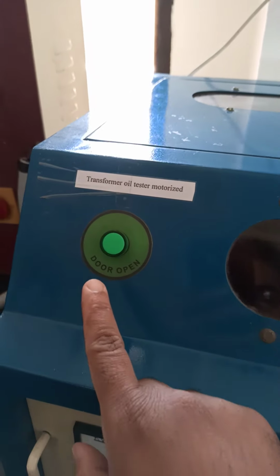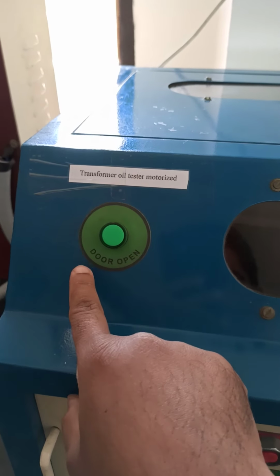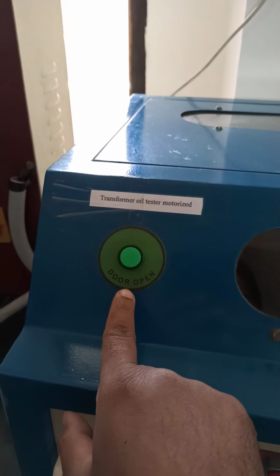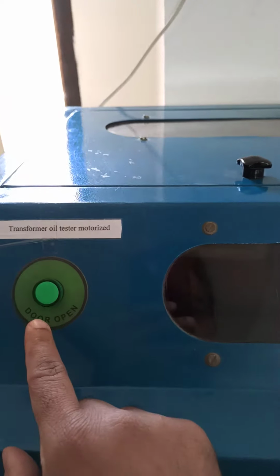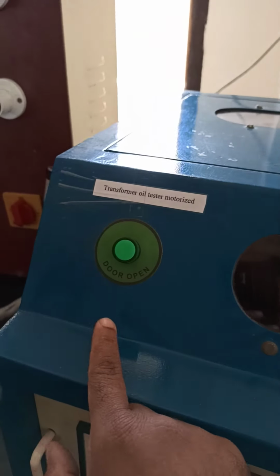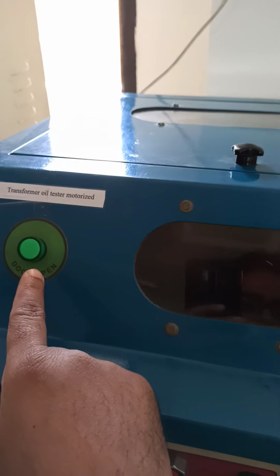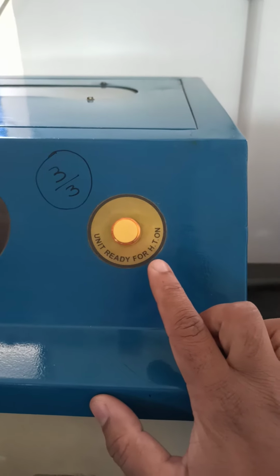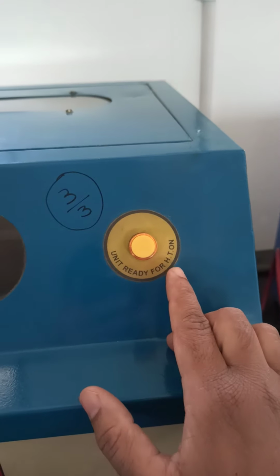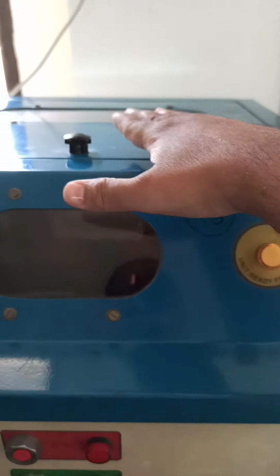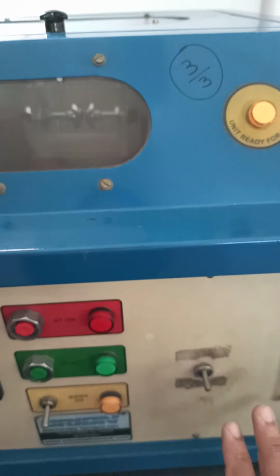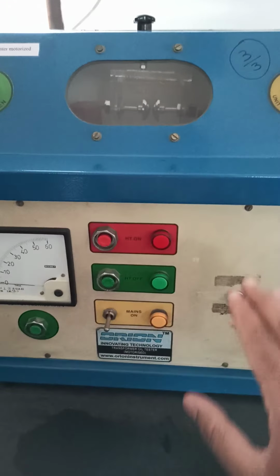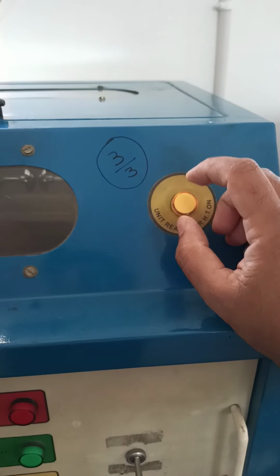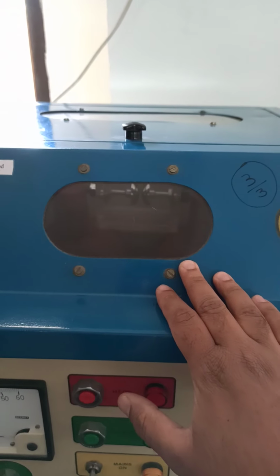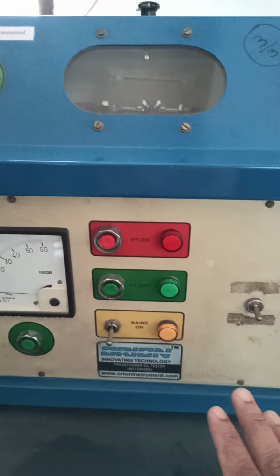As you can see here, there is one indicator which is showing that the door is open. If this door is not properly closed, this indicator will turn on. I will show you that also. If it is closed, then this will not glow. Okay, so this indicator is given for that. Another indicator is there which is showing that the unit is ready for HT on. So whenever this lid is properly closed and when we do the settings over here, this indicator will glow, which tells us that yes, this unit is ready for the test. Okay, so let us see what we have here.